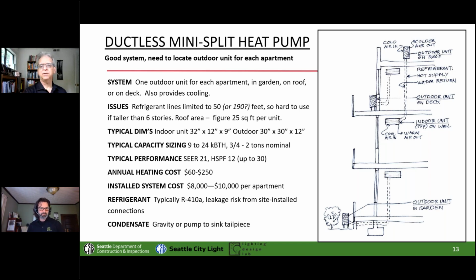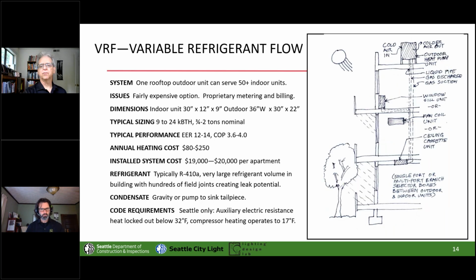Right, and any of these heat pump systems, see this one we're saying 8 to 10K per apartment. That's in context of, I guess, market rate all in is probably $300,000 or $350,000 per apartment. So it's increasing costs somewhat. VRF is popular for bigger buildings. By the way, the diagram here doesn't show the fact that the VRF actually feeds to these boxes that each box then can fan out to a large number of different units and provide the asked for heating and cooling to those.